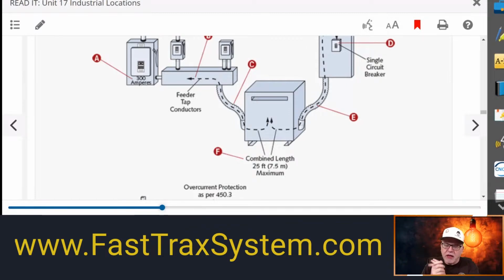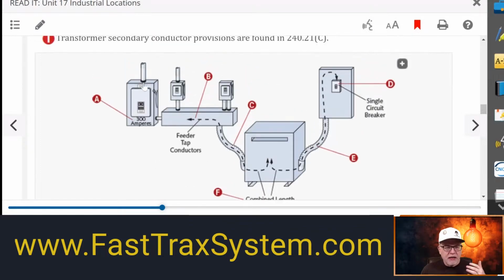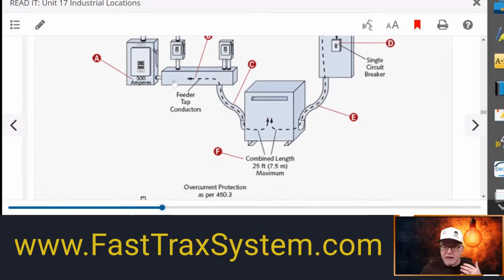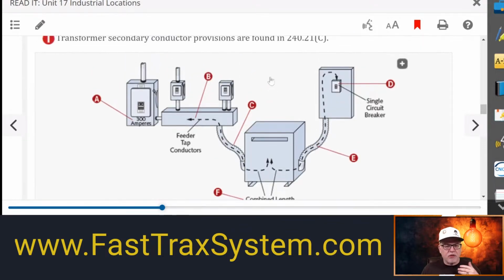Now, why would you do this? A lot of times this can be done because maybe this is in a utility room or somewhere where we need to change voltages for another type of load. Maybe it's the lighting. So maybe this is all 480 stuff here, and we need to get some 120/208 loads. So boom, they put in a transformer, tap it here, bring the 480 in, and then boom, we can get a panel that's going to do maybe the lighting and that type of thing all in the same room. So this is a scenario where you may have this transformer.